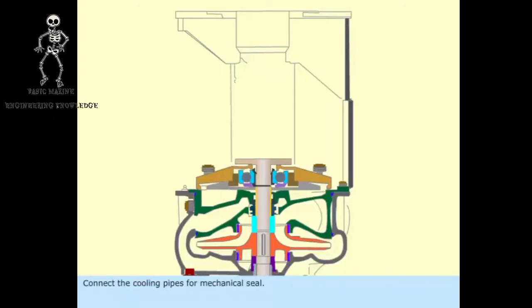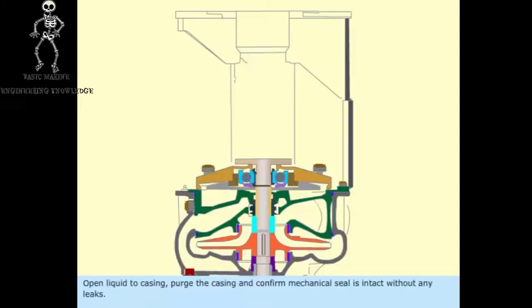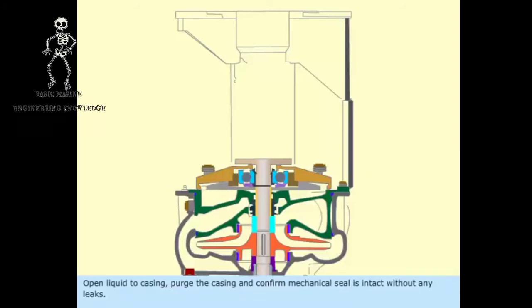Connect the cooling pipes for mechanical seal. Open liquid to casing. Purge the casing and confirm mechanical seal is intact without any leaks.